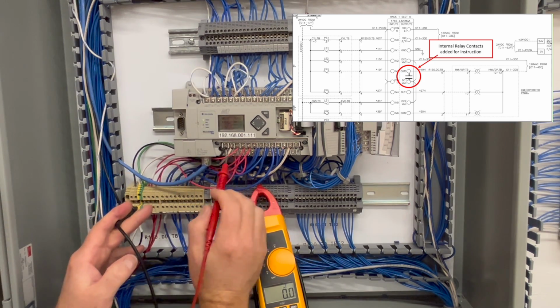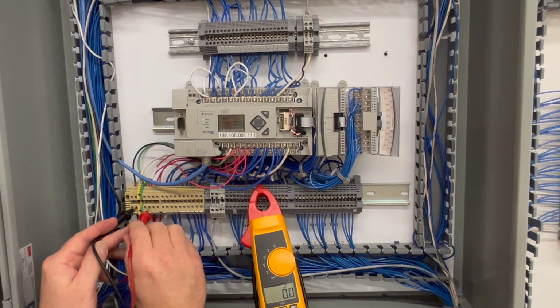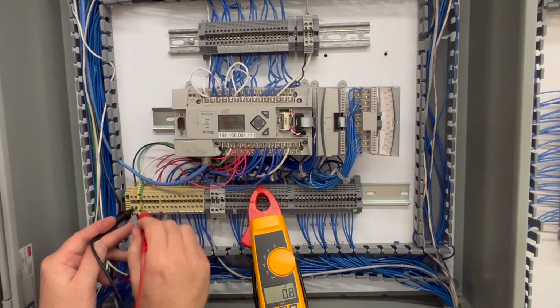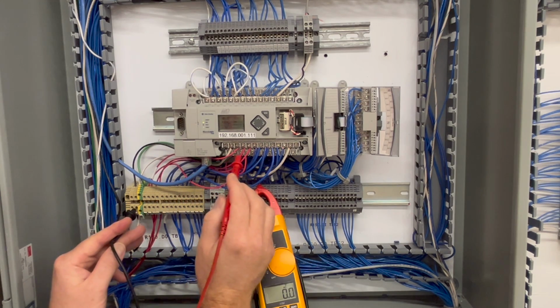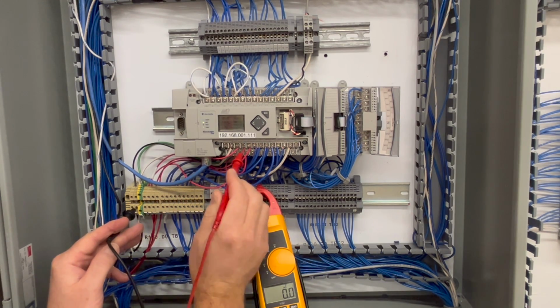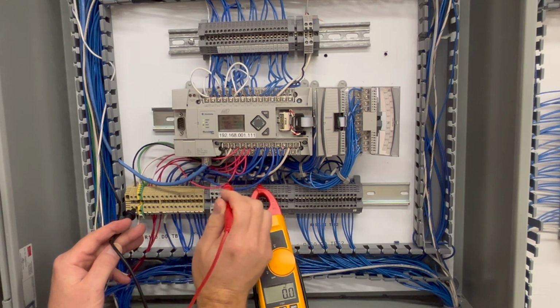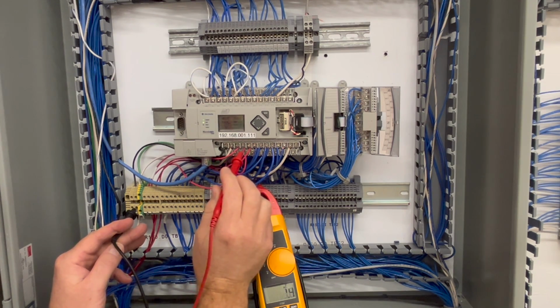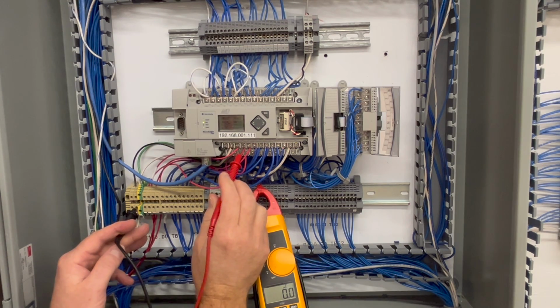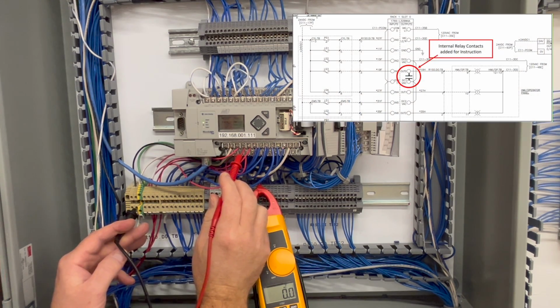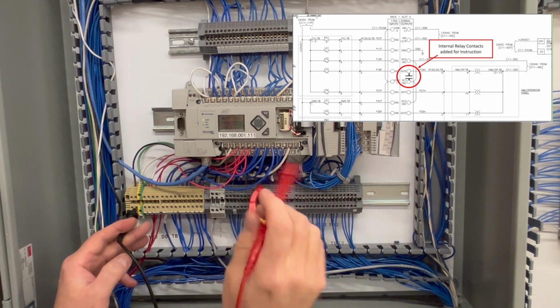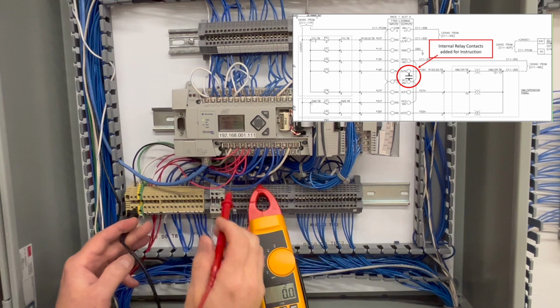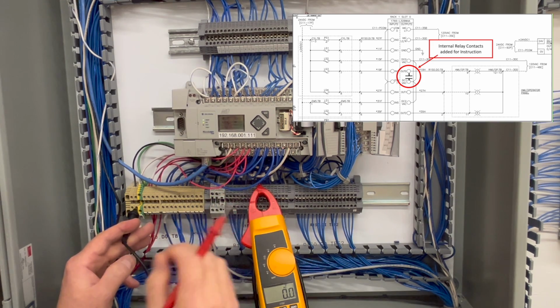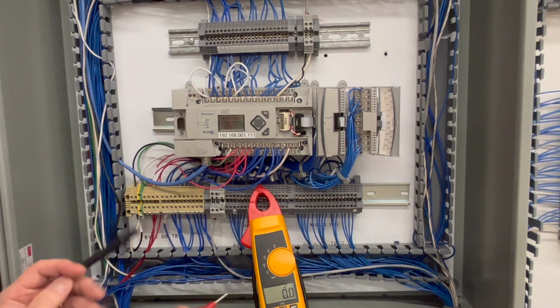So now we know, and this is how we verified it. So we just traced the power back, making sure we're on this neutral, to where the power should be. If this was on, we should be getting 120 volts through here, because this would close, electricity would flow through the power line, through here, through there, and you can see this on the schematic diagram, out to the light. So it's not the light that's bad, it's not the wiring that's bad, the PLC output is actually bad.